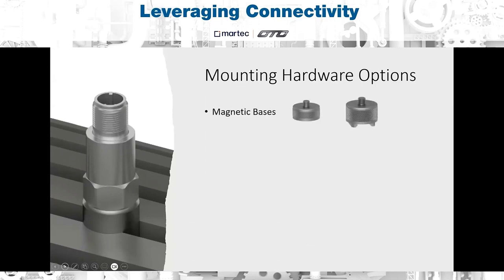The first option is a magnetic base. These are commonly used for portable measurement. We offer these magnets in either a flat surface or 2-rail design. The flat surface magnet provides a higher frequency response. However, it is not always an option based on the machine being measured. If you are not able to find a flat surface on the machine, then you can always utilize one of our 2-rail magnets, and these are designed to take readings on curved surfaces.